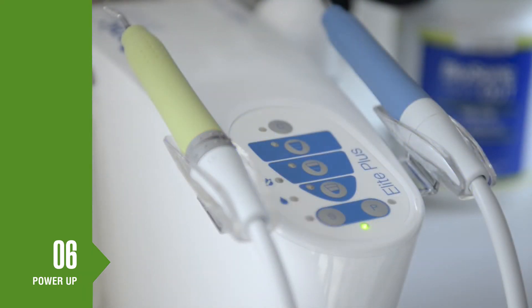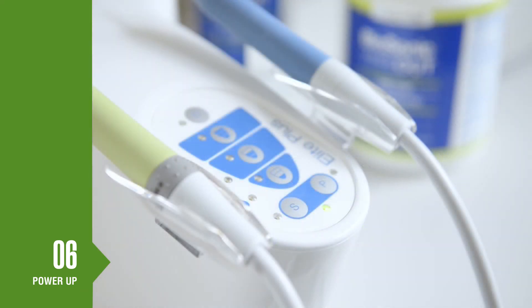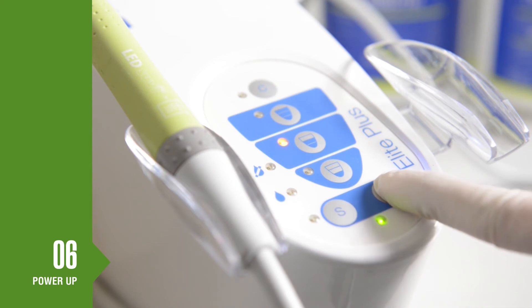If five blue lights on the control panel are flashing, check that your foot pedal is properly connected. If set up properly, the unit will go into standby mode after about 20 seconds and only the green light will remain on. To force standby mode, hold the S or P button for three seconds.